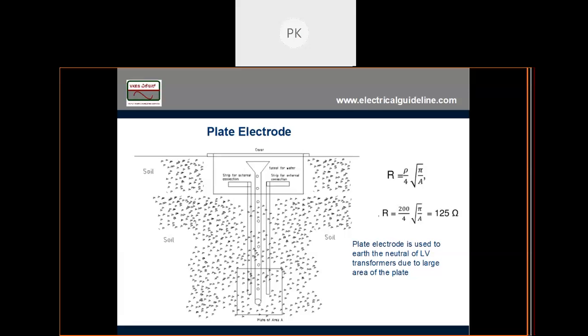In this plate earthing, I have given one separate pipe so that it will carry water, and some holes so that when we water it, the water will come out. Then we have a strip here for external connections, and a cover to remove for inspecting. The connection to the plate is normally welded. Since it is iron, we have to weld it and then paint it again because the galvanizing is disturbed.